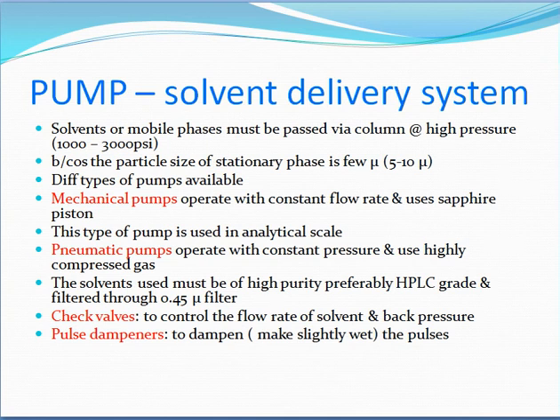Check valves are used to control the flow rate of solvent and back pressure. A pulse dampener is used to dampen and smooth out the pulses in solvent flow.